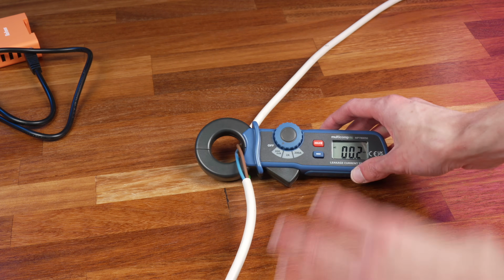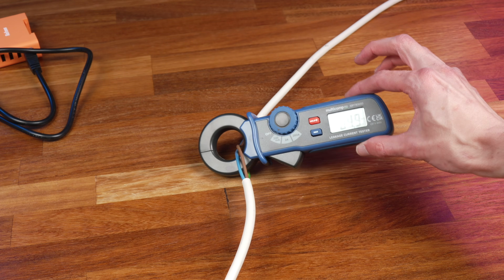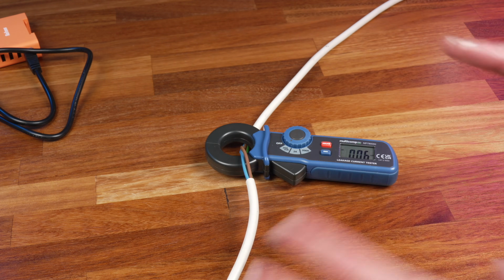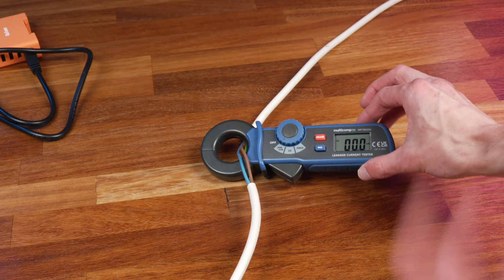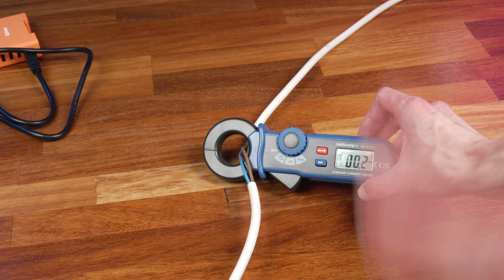There's maybe a very small current flow here, and that represents the earth leakage. Now, that's another use for this sort of scary extension lead. It's quite useful for measuring the earth leakage of an appliance using a clamp meter like this, if you want to diagnose, say, things like RCDs tripping, but it's not any value that's going to be useful for measuring your power consumption.